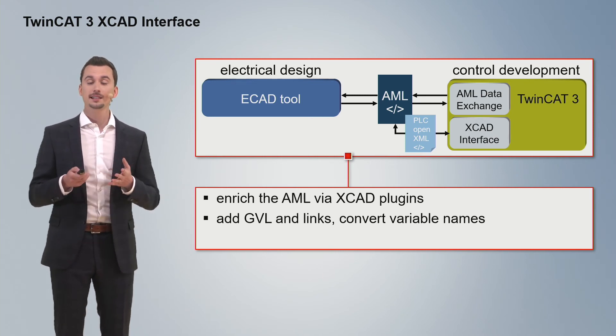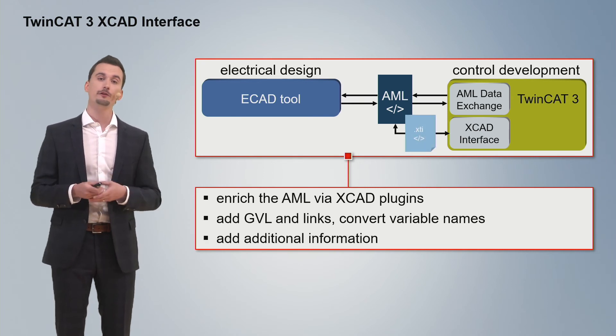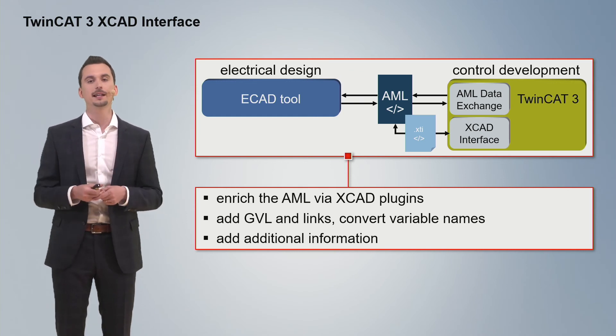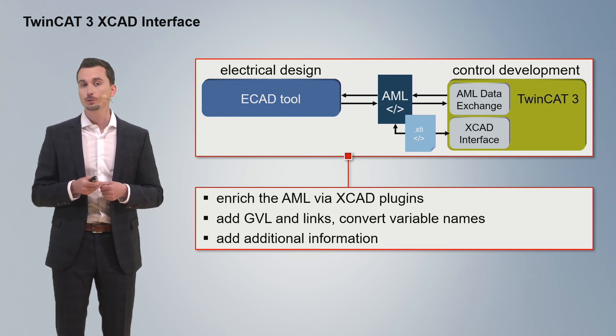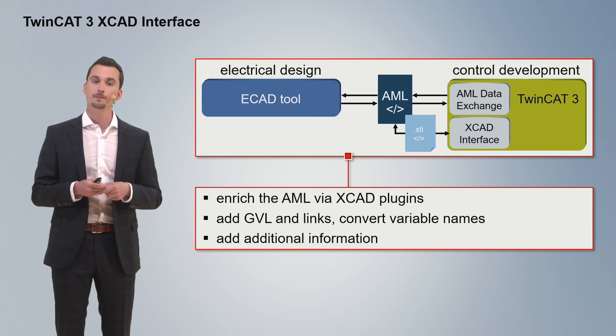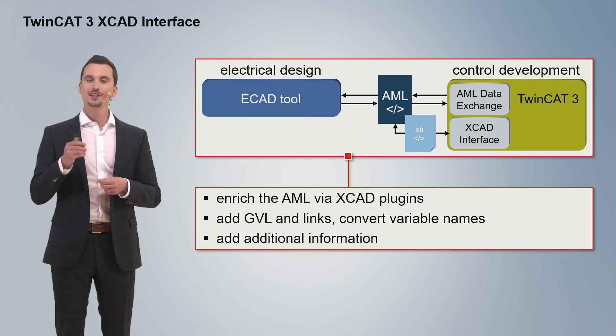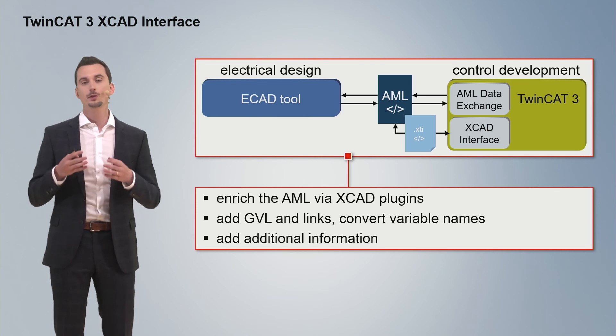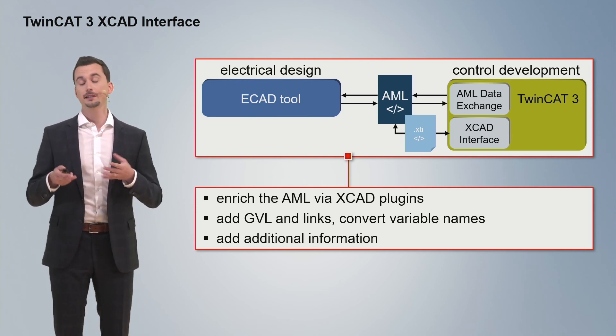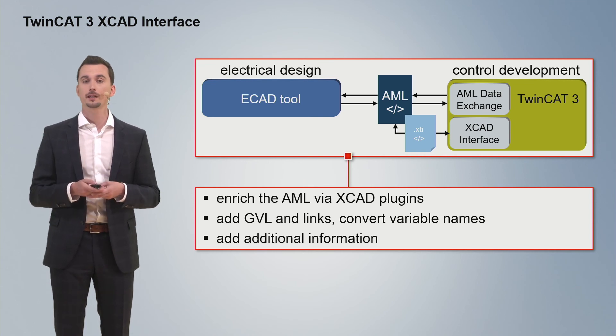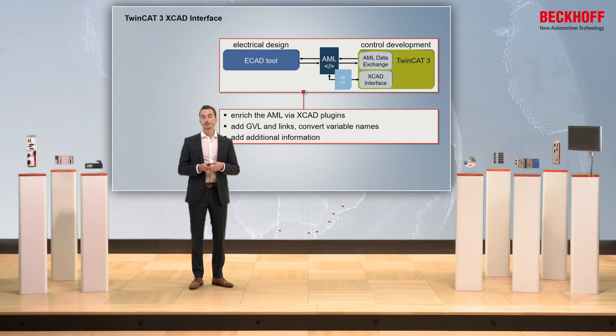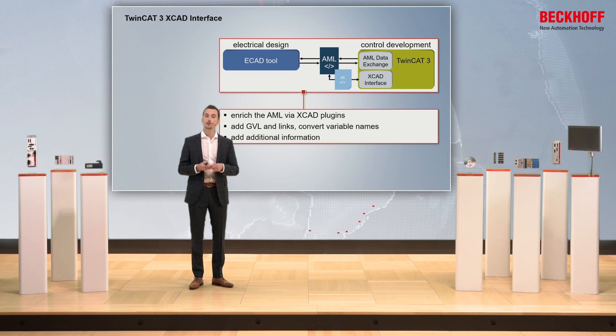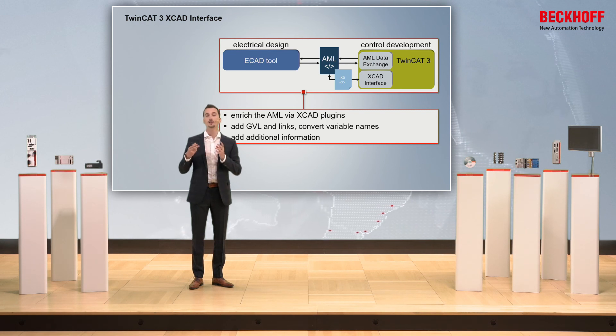You can also use XCAD to add further information, like for example a comment which is already added on the ECAD tool side — just import it and add it in TwinCAT 3 in the IO topology or on the variable declaration. In addition, it is also possible to define IO templates. So if you have specific terminals which are always configured the same way, you can save a template and use it during other imports into your TwinCAT project. All in all, with the help of the new XCAD interface, you can increase the efficiency of your engineering workflow from the point of view of data exchange between the electrical design and the control development.